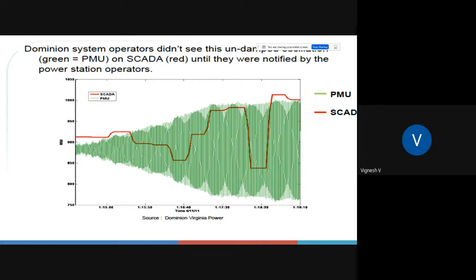For example, if there was an event with small signal oscillations that were unstable, the SCADA data was misleading, whereas the PMU data exactly shows a growing oscillation. So the operator can be aware well ahead of the situation going catastrophic, getting an idea before the event actually occurs. Relying on SCADA data, which does not show any oscillations, leads to a misleading decision, whereas PMU gives much more insight into system operation.